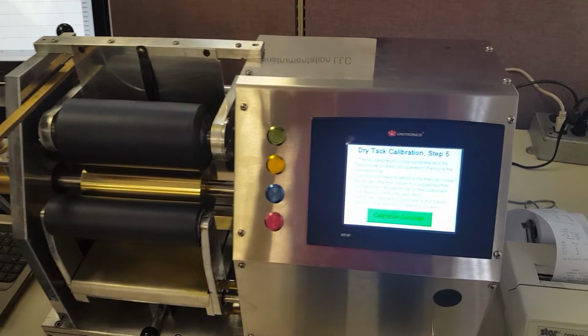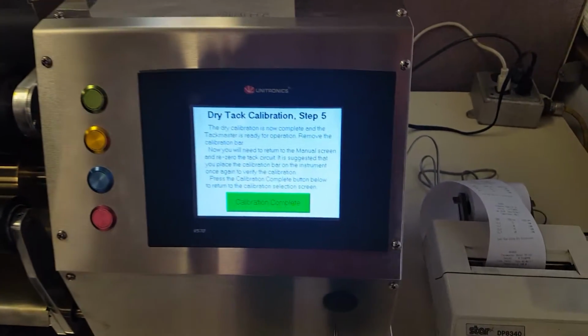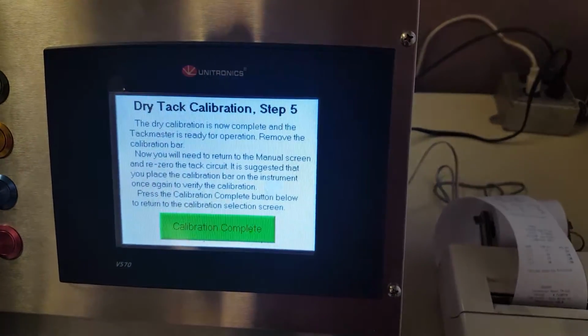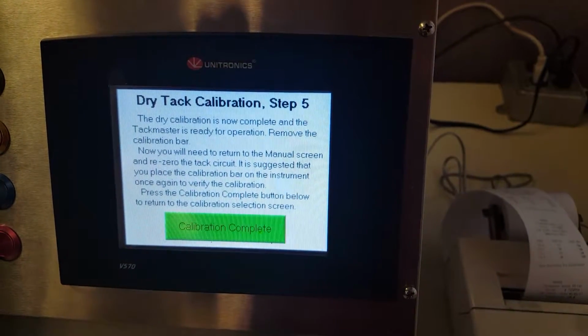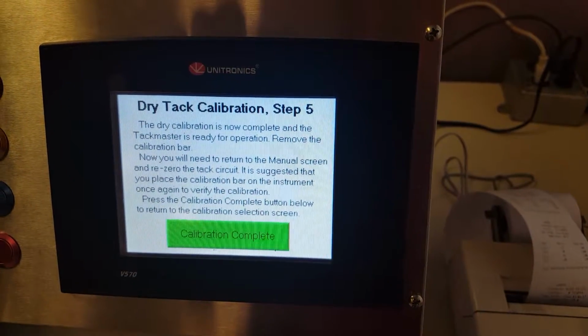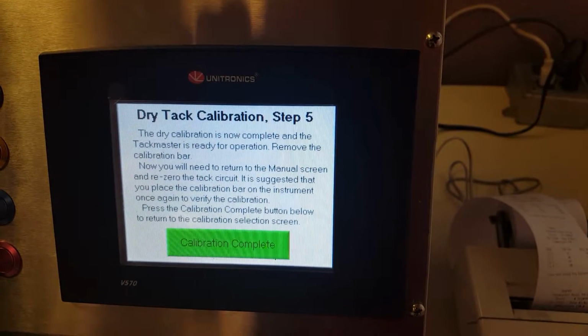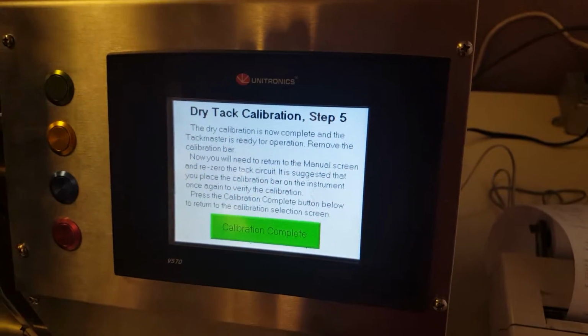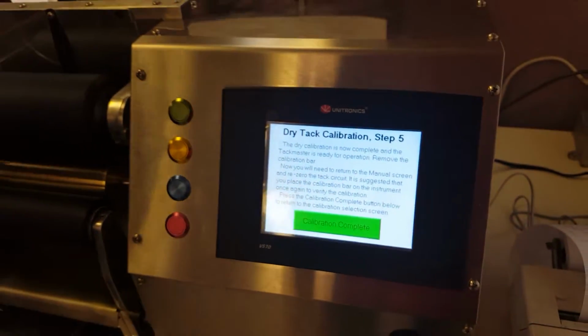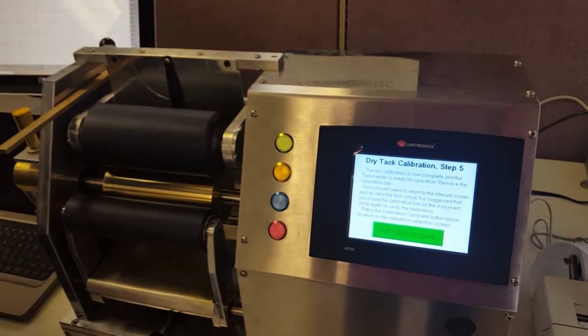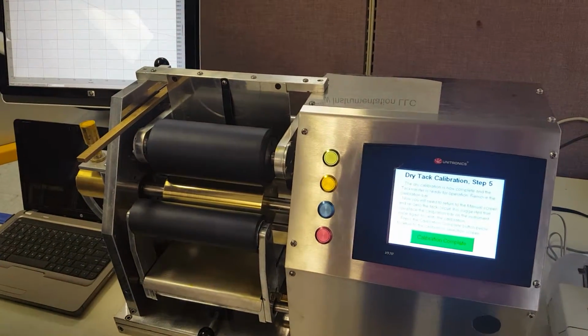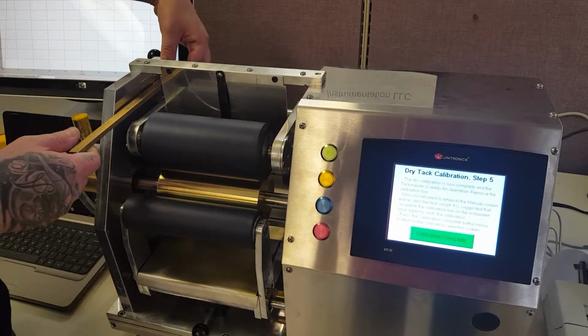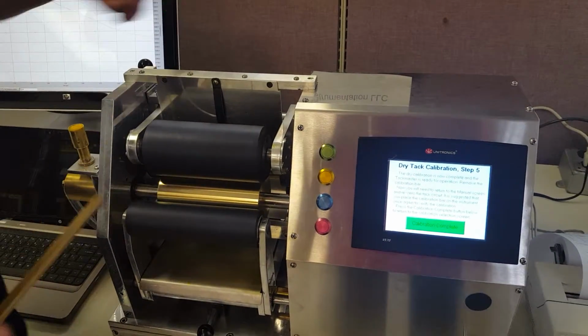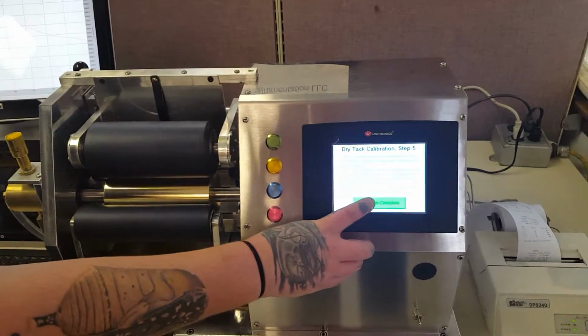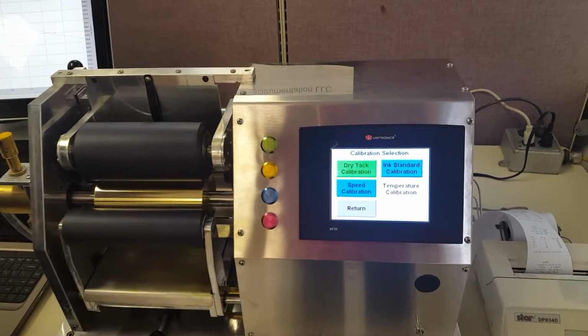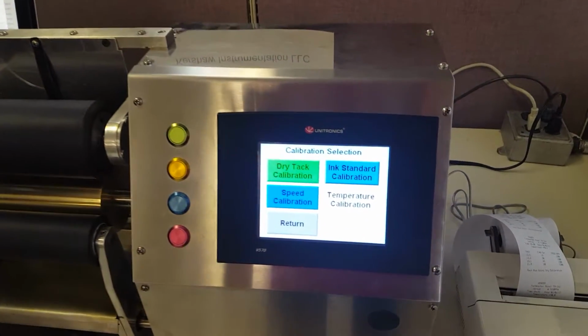This brings us to another text screen that basically tells us our calibration is all complete and that it should be reviewed in our manual test screen by going into a manual test and verifying it by hanging a bar on here while running it manual, which is something you can see in the introduction video we had. And then it also tells us we want to remove this bar here, and we want to hit the calibration complete button. This brings us back to our calibration selection screen.